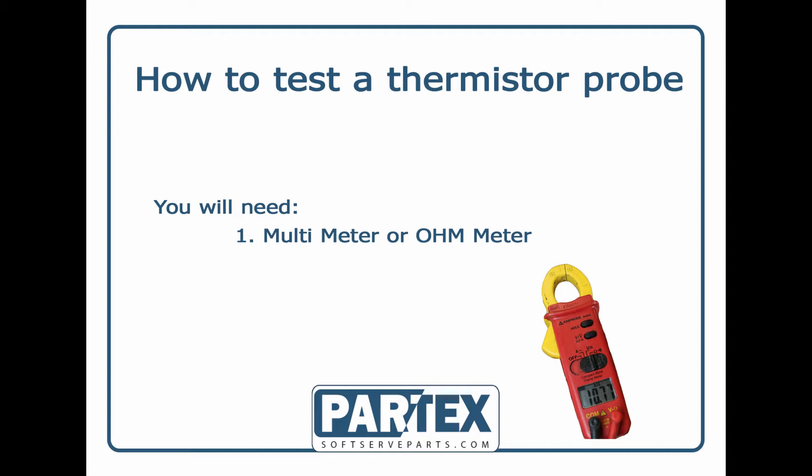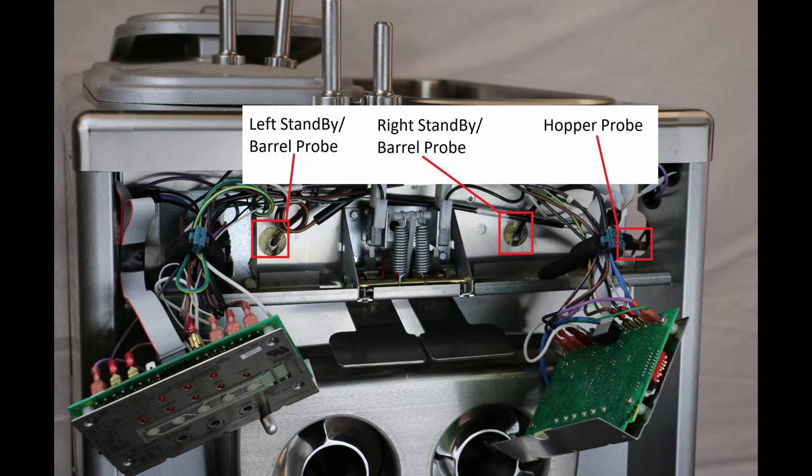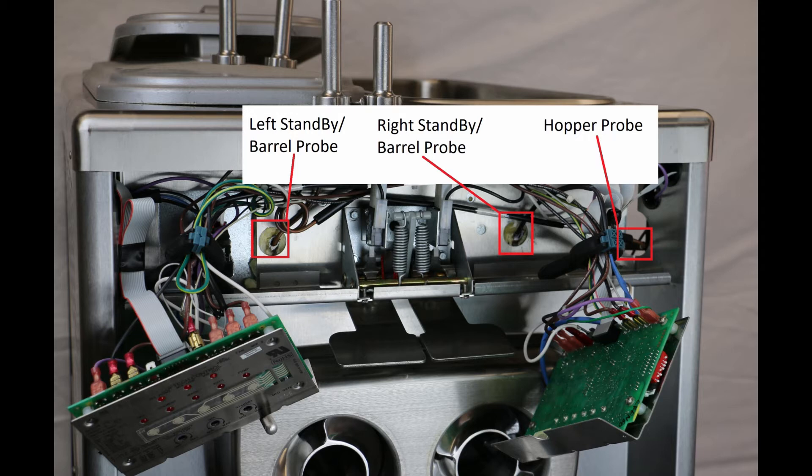The hopper probe senses product temperature whenever there is product in the machine, whereas the left and right standby probes or barrel probes only come into play when the machine is in standby mode. If your machine's not maintaining safe food temperatures in the hopper or either freezing cylinder and adjusting the machine won't work, there's a good chance you have a failed thermistor probe.